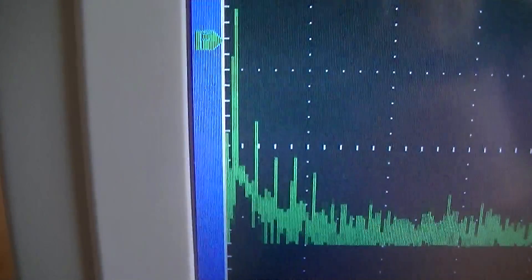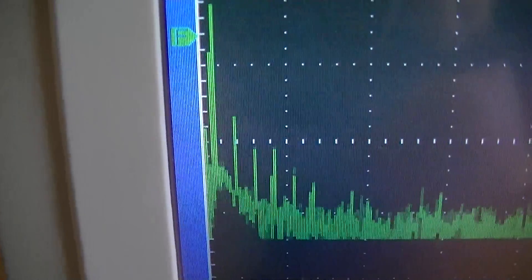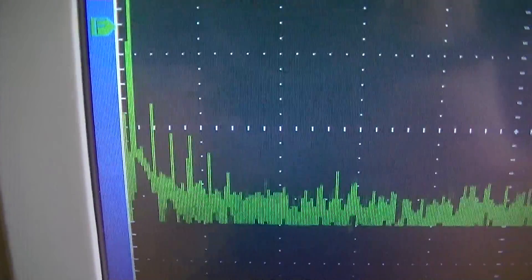You can see all the harmonics down on the left hand side. The big spike is the 60 Hz fundamental frequency, and you can see we've got a bunch of other harmonic spikes in there.